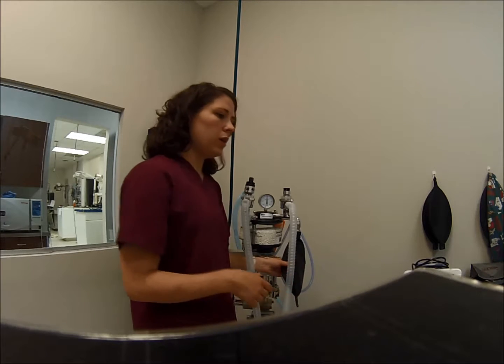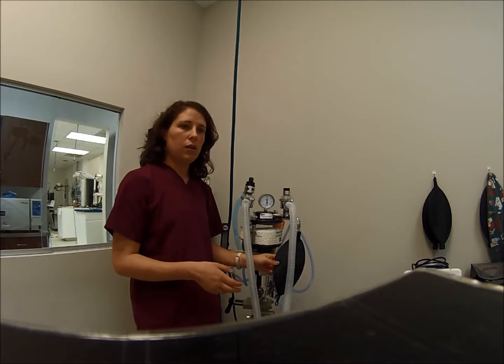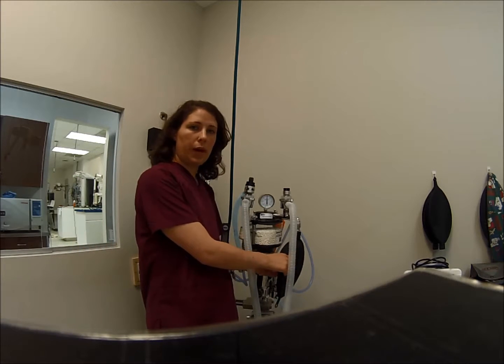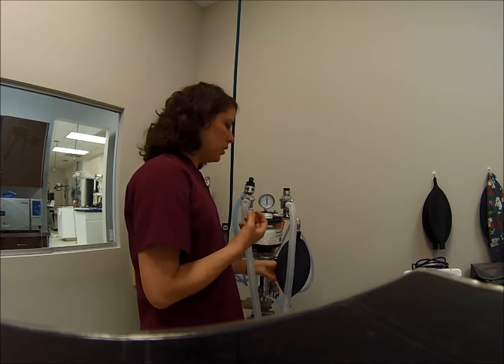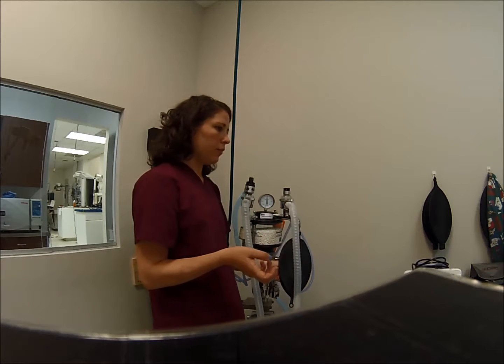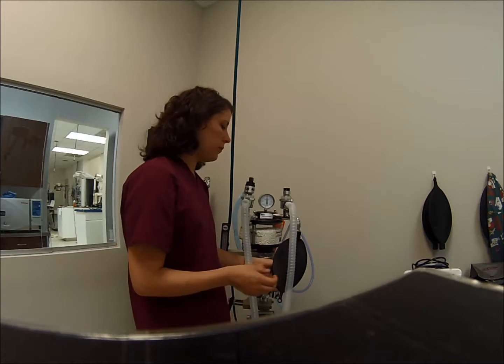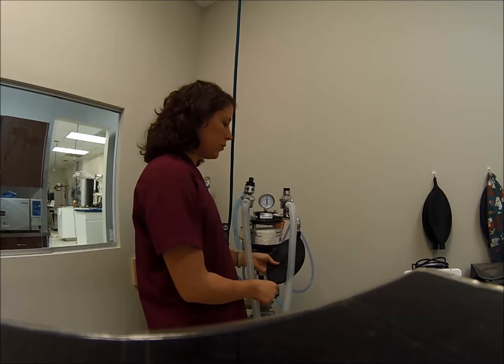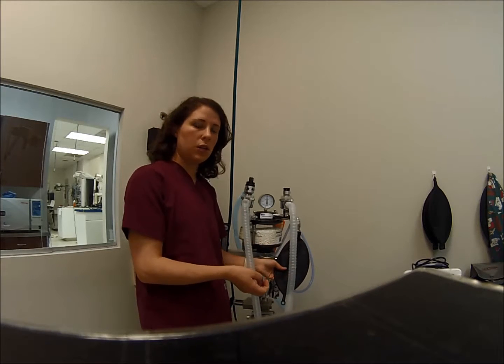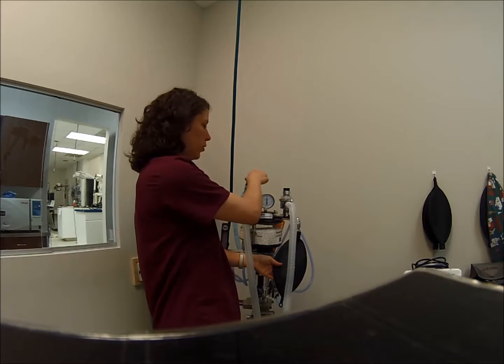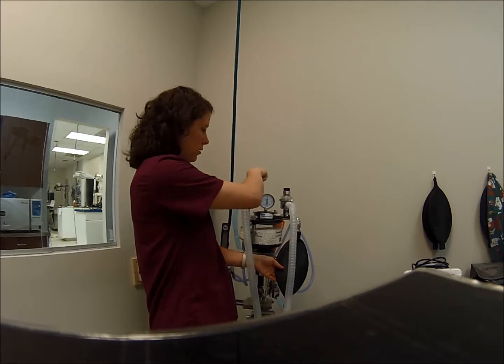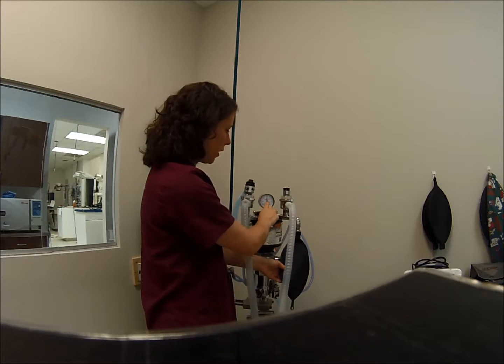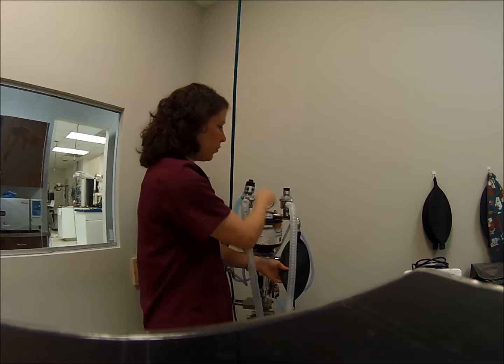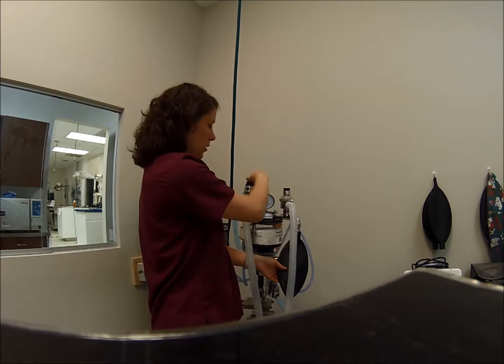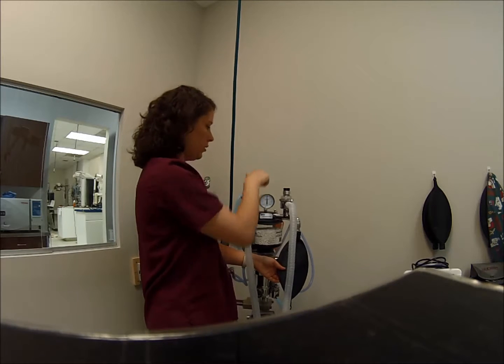The bag allows the patient to breathe in gases that are stored within the bag. When the patient inspires, the bag will deflate, and when the patient exhales, the bag will inflate. This can also be used, like I said, to manually bag the patient, in which you'll want to close your pop-off valve all the way, squeeze your bag to a pressure no higher than 20 centimeters of H2O on the manometer, which I will get to next, and then open up your pop-off valve again.